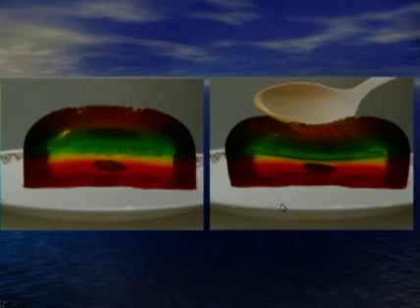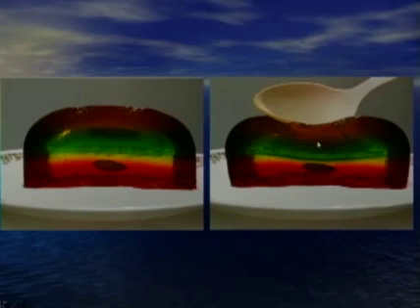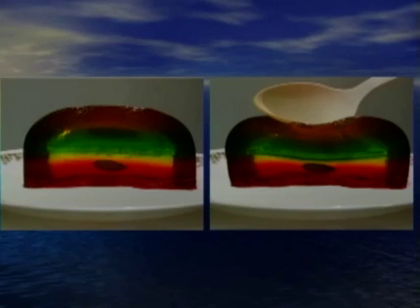An easy way to explain the displacement elastography algorithm is to consider an almond in a bowl of jello. If we deform the jello with a spoon, we change its shape because it's soft. However, the almond is hard and does not change shape no matter how hard we push. The ultrasound system looks at frame-to-frame differences during pressure application — if tissues change shape like the jello, it codes them as soft; if they don't change like the almond, it codes them as hard.